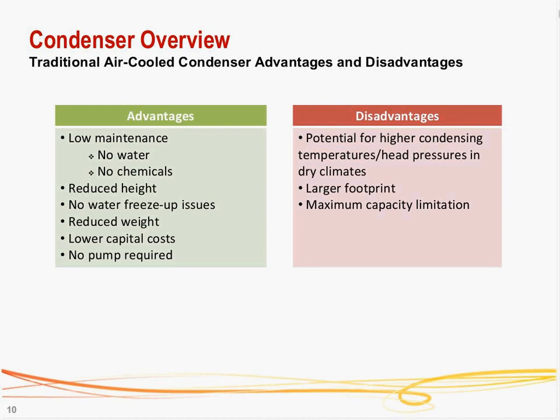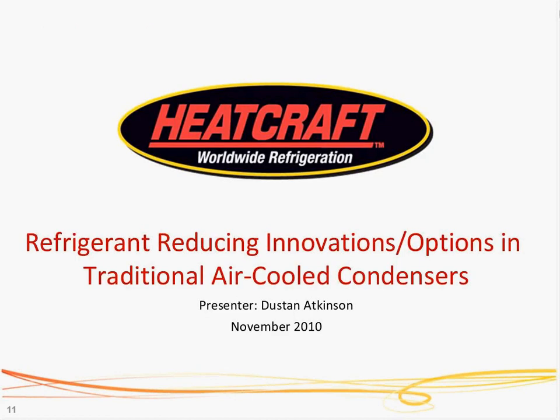There are, of course, trade-offs there. There is the potential for higher condensing temperatures and head pressures, particularly in dry climates. There is the potential for a larger footprint, and there is a point at which the capacity is just beyond what you would want to use an air-cooled condenser for. That's way beyond what you would run into in pretty much any supermarket application, but the maximum capacity limitation does exist. I'm going to step through some key refrigerant-reducing innovations and options in traditional air-cooled condensers.